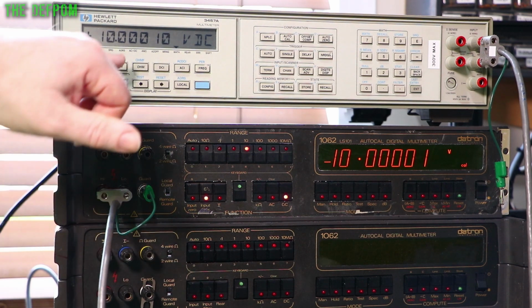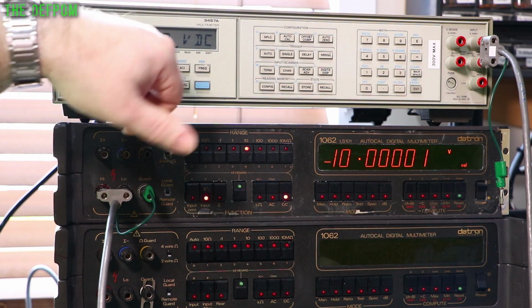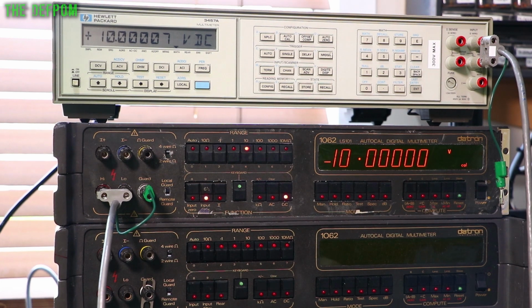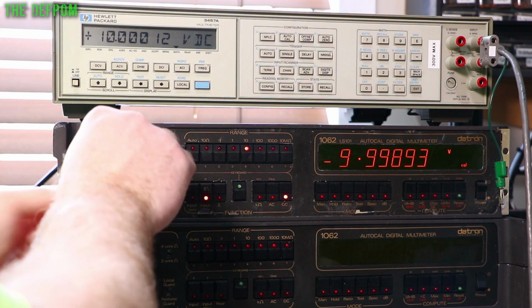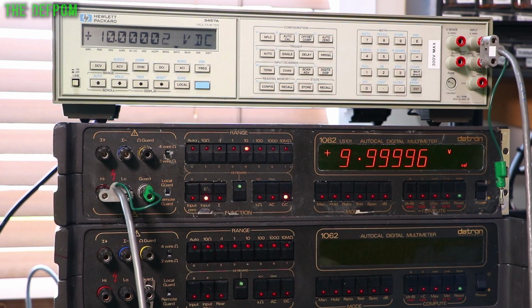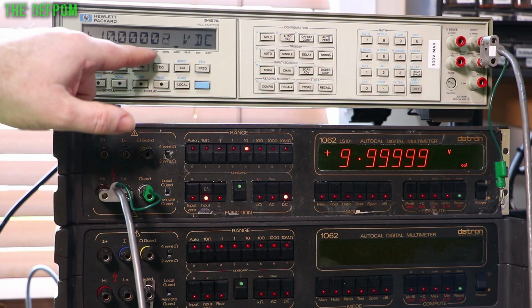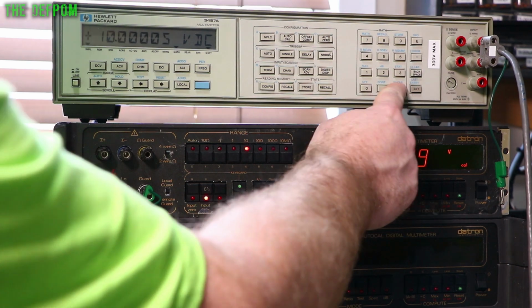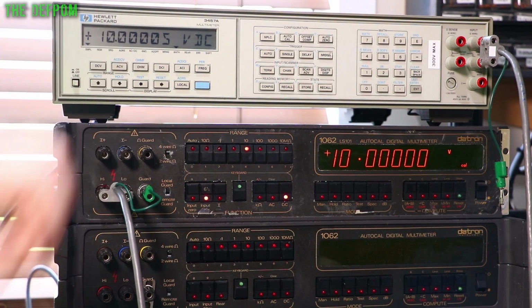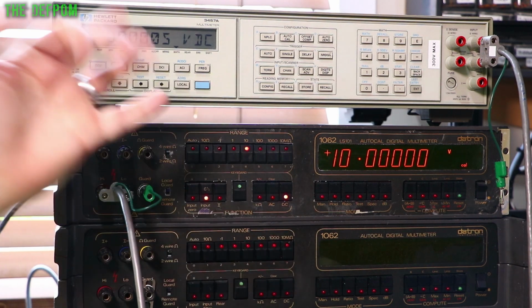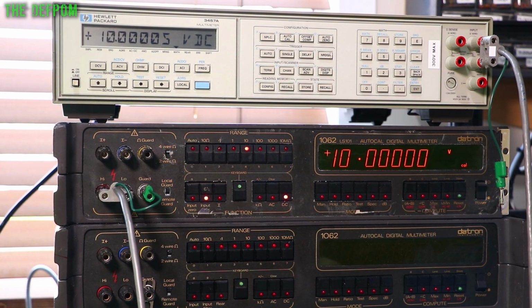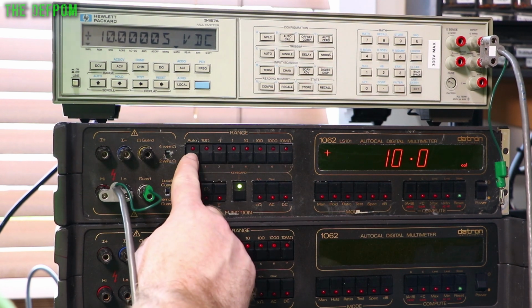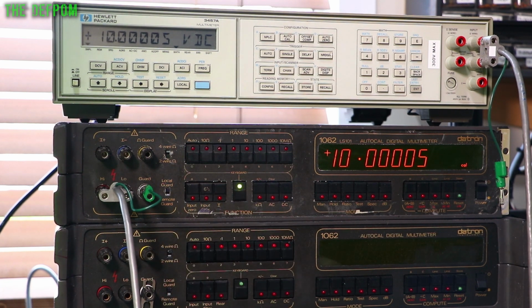Okay. Now, I'm thinking my calibrator is slightly high because this meter is reading slightly high, so I probably have calibrated very slightly off. So I'm actually tempted to correct that because this one is reading slightly high. So if I recheck that way, what I could actually do is tell it that this is the number. Right, if I switch the filter on, that'll average it out, and that'll tell me exactly what I should be setting it to. Right, so about 5 counts out, which is like negligible really. It's almost nothing, not really worth worrying about. But for the sake of completeness, let's do it properly. 10.00005, gain. Okay, so that now thinks that is that voltage, which is what it should be actually.